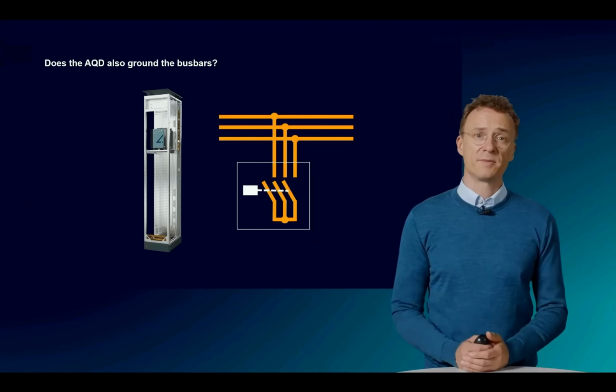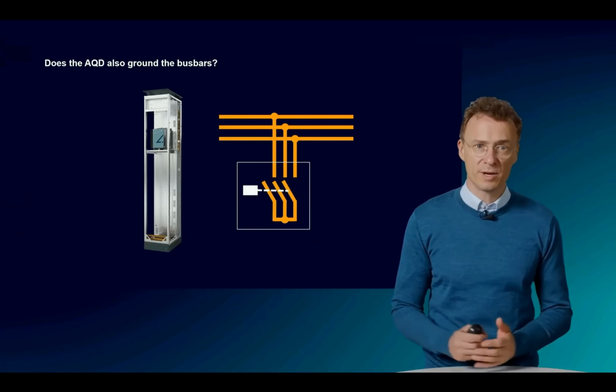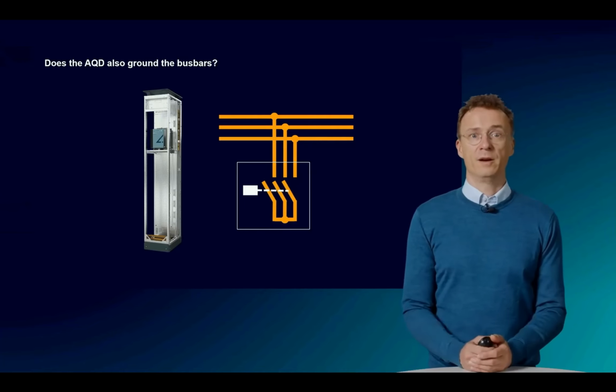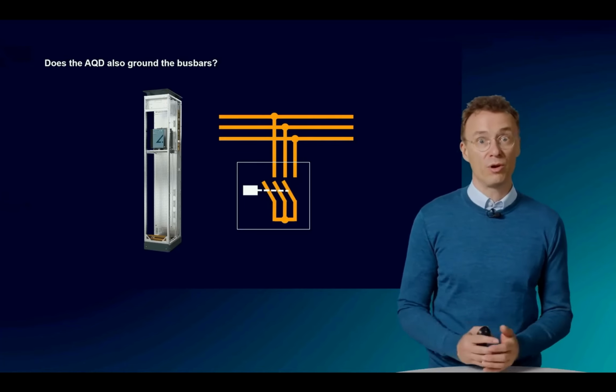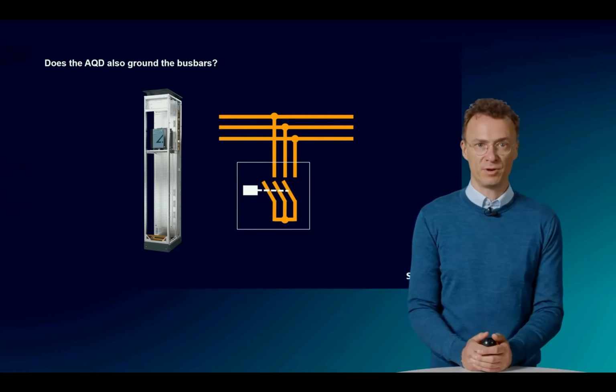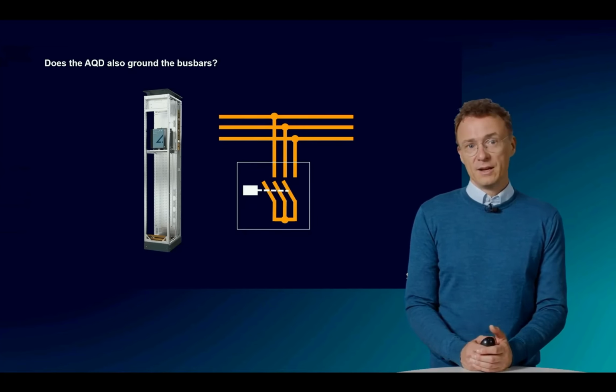And the next one is, does the AQD also ground the bus bars? No, the AQD creates an all-pole or a three-phase short circuit on the main bus bar. Next question. Can the system indicate to other protective IEDs, intelligent electronic devices? The system has a relay interface to signal to other systems or such IEDs. That way, it can also be integrated into other systems.